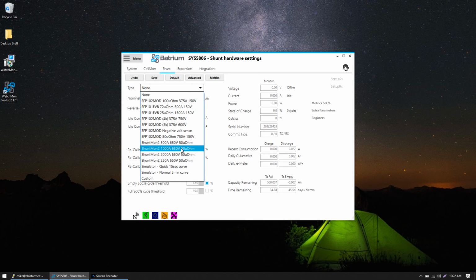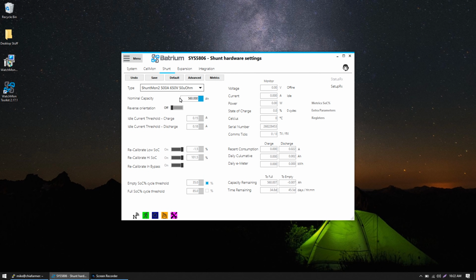The shunt I'm using for this test is a Shuntmon 2 500 amp shunt block, and my nominal capacity is 560 amp hours, because I have two parallel strings of 280 amp hour batteries. So I'll click Save, then back to Menu and Chart.